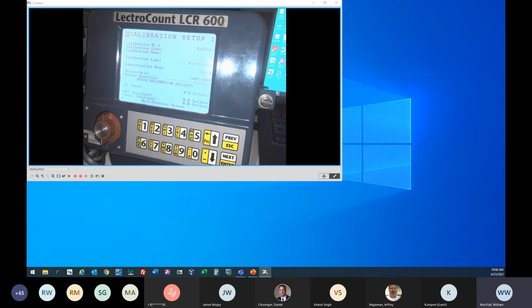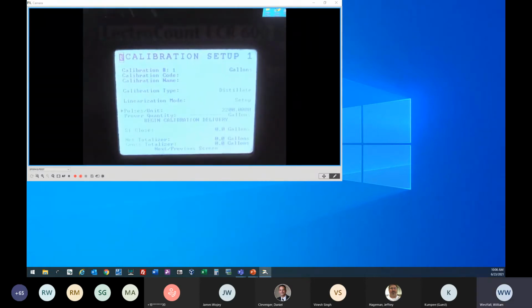Now, in order to start calibration on any of these electronic registers, they do need to have a starting K factor. Most of the time, from the factory, they're going to start out at a default K factor of 20. In order to change it, let's say we want something closer to an M7, which is going to be somewhere around 2200. If we just enter in 2200 pulses per unit, in this case pulses per gallon, that'll get us pretty close to start with. Let's turn the light off here, see if you can see that any better. There we go. It looks a little bit better.